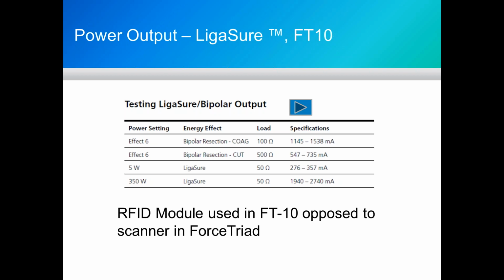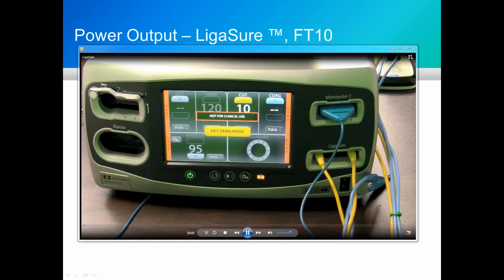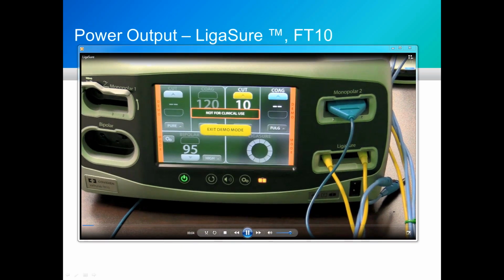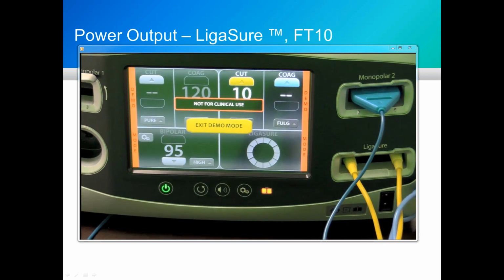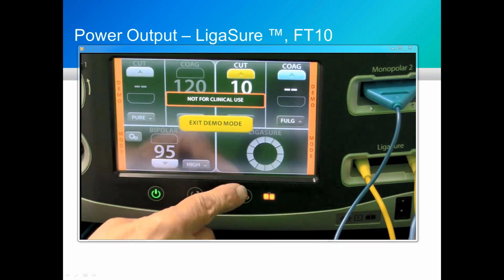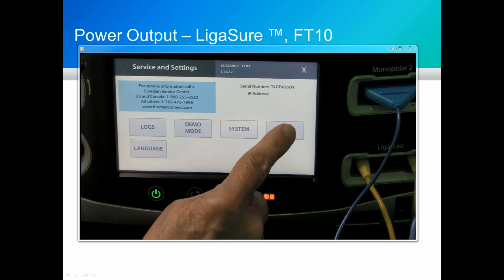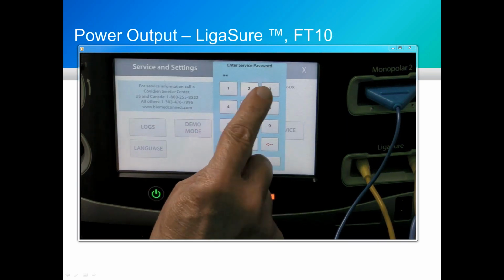We're still testing, of course, closed loop, but we don't have that varying tissue resistance, varying tissue density. So with this particular unit that I'm doing my testing on, we're going to see that we're measuring about 2.2 amps. One other thing with the LigaSure port designed as it is, you can't get right angle test leads in there. So I've borrowed some other test leads that I was using for my foot switch connectors before.